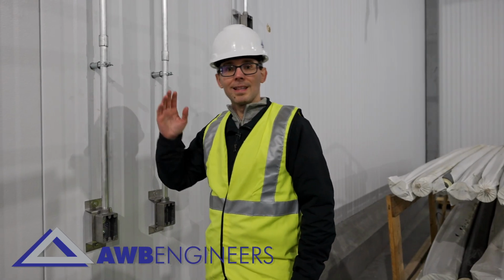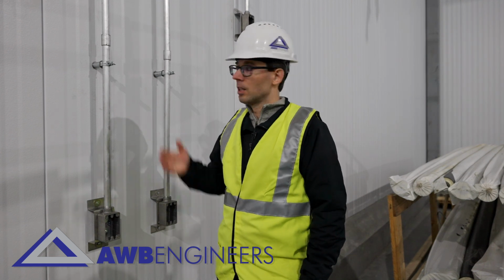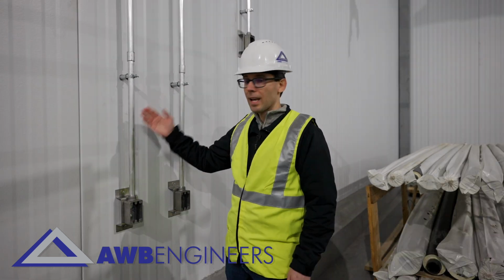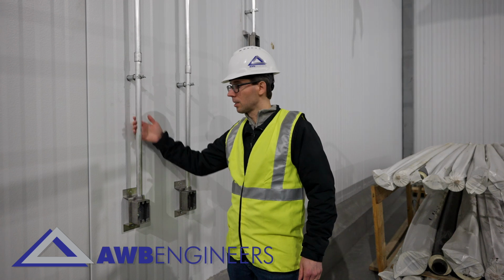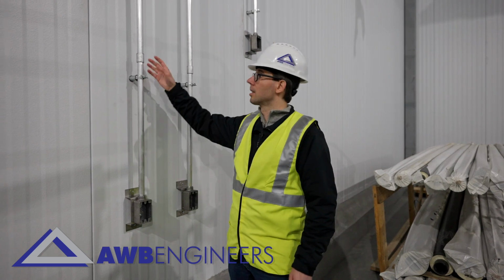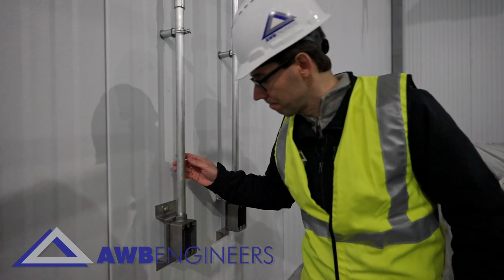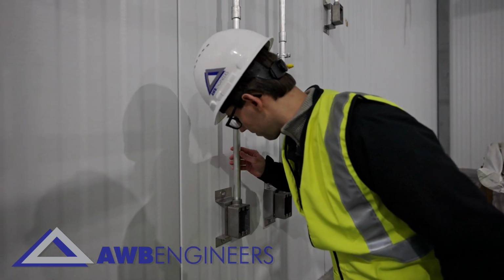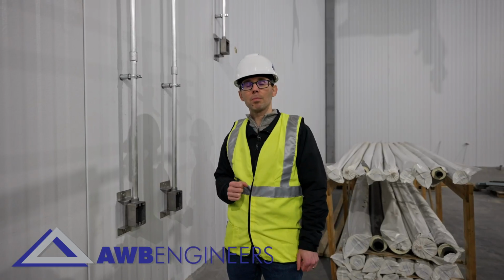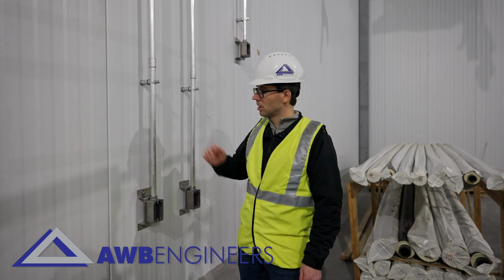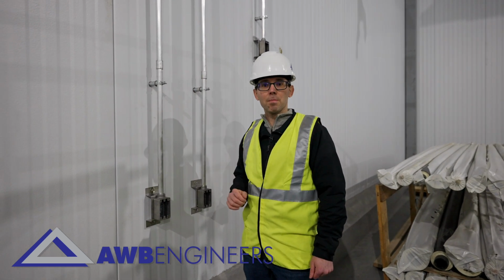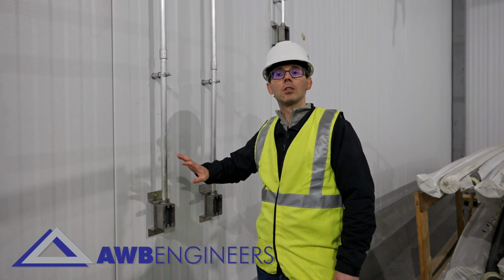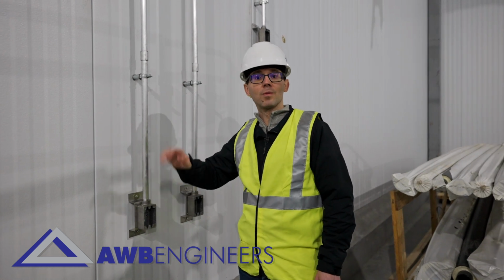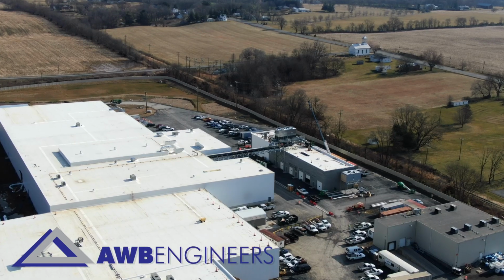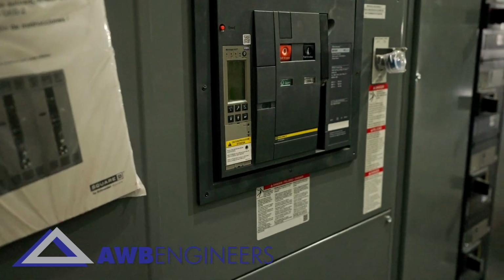This detail shows that any conduit, any piping needs to be installed away from the wall and allows space to clean the entire conduit and everything related with that. When the installation is done, it will incorporate functionality for high pressure washdown application. In this case, they'll be able to clean this with high pressure, hot water and stay safe and bacteria growth free.